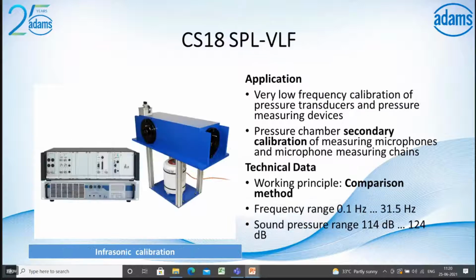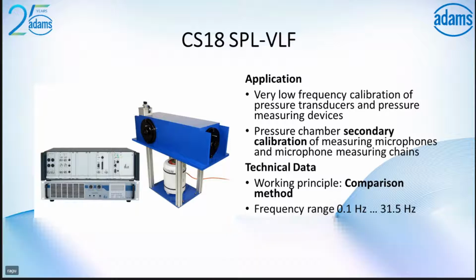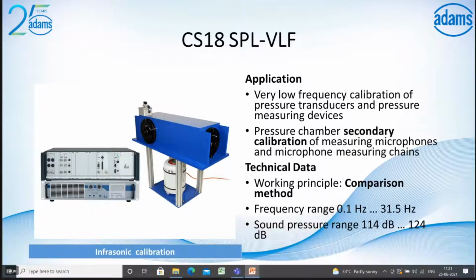And CS18 SPL for pressure field microphones at very low frequency. It's based on infrasonic calibration. This method is specially developed for the calibration of general types of measurement microphones between 0.1 Hz and 31.5 Hz. And it includes the design of an active comparison coupler, experimental low frequency reference microphones, and new methods for frequency response calibration. One method applies an electrostatic actuator, which requires a low pressure measurement tank, and the other requires a reference microphone, which needs to be calibrated. And for the secondary calibration of measuring microphones by comparison method from 0.1 Hz to 31.5 Hz, the maximum you can go up to is 124 dB.